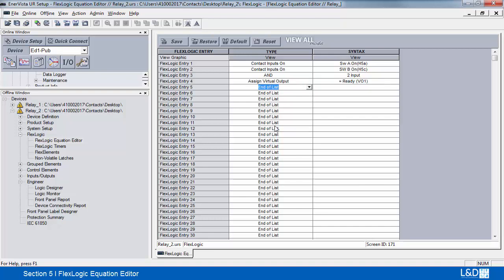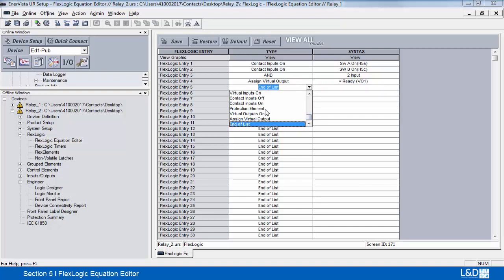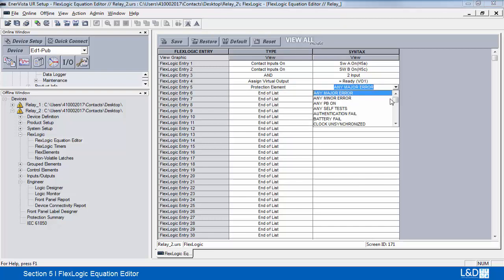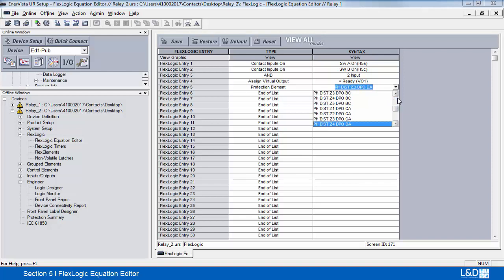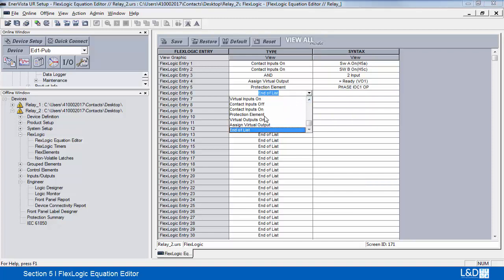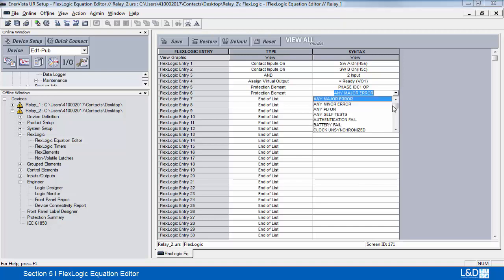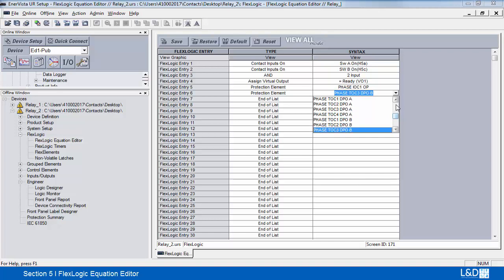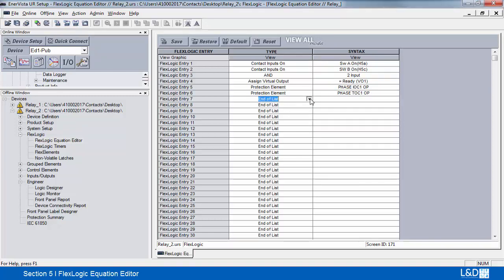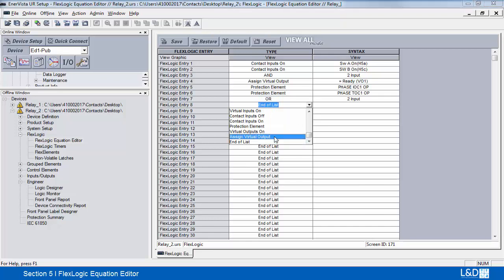We'll create another circuit for protection. So what we'll do is we'll take an IOC and a TOC function, pressing the letter P until we get down to the protection element of choice, pressing the letter P again. And we're going to OR these together, then we'll assign this to a virtual output.